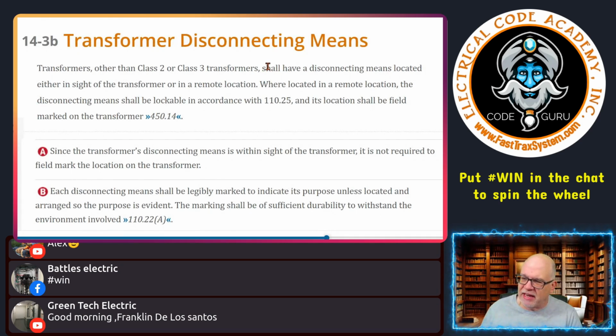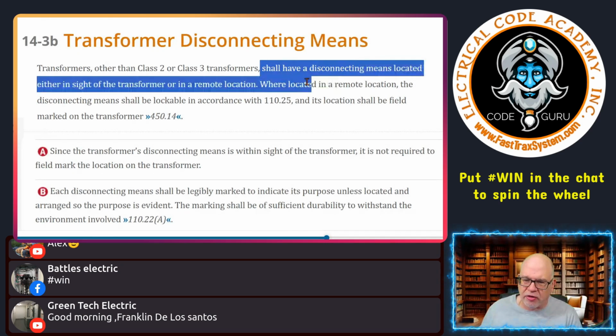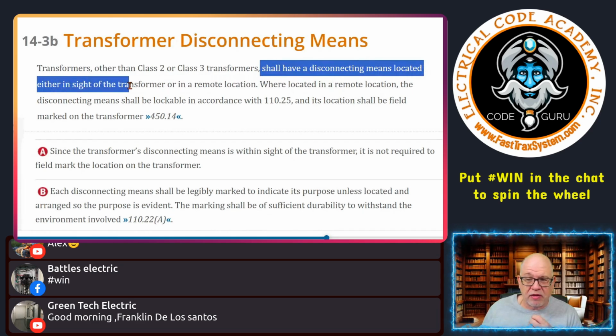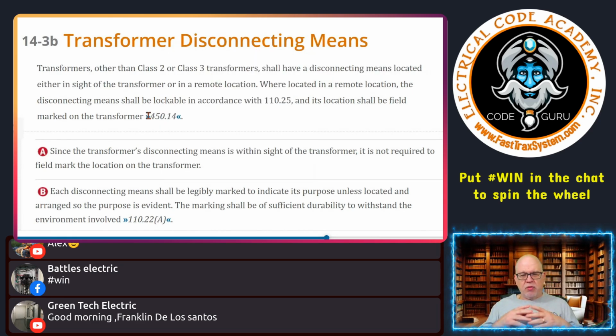Shall have a disconnecting means located either in sight from the transformer. So that's the first one. If I'm going to do a power transformer, it could be a primary 480, secondary 240, or a primary 480, secondary 240/120, or a primary 480 and a secondary 208/120. Depending on the type of transformer you have, I have to have a disconnect either within sight.